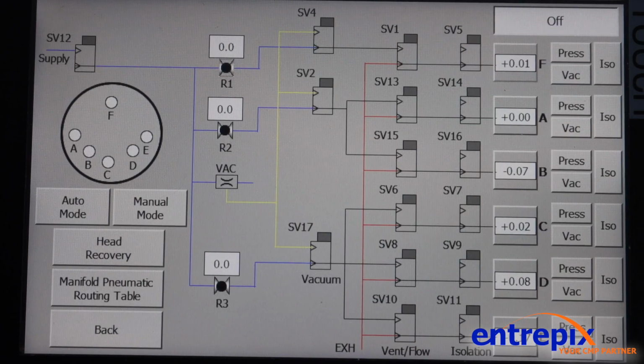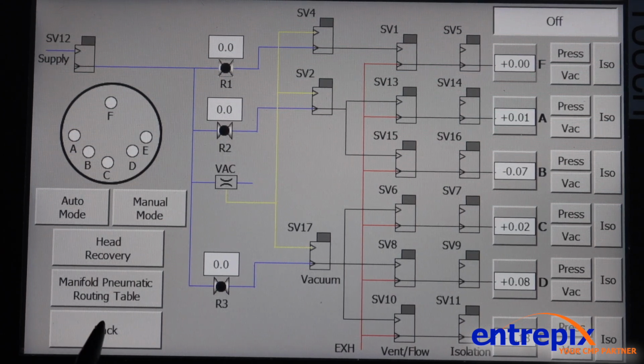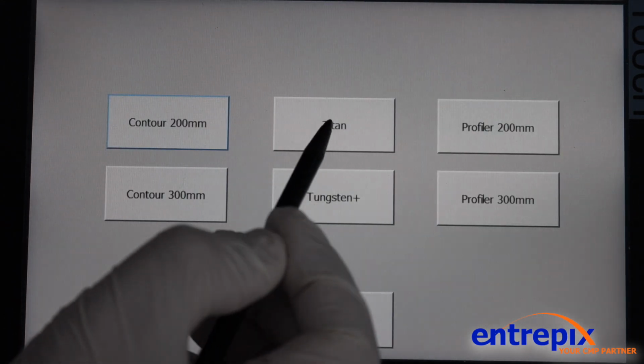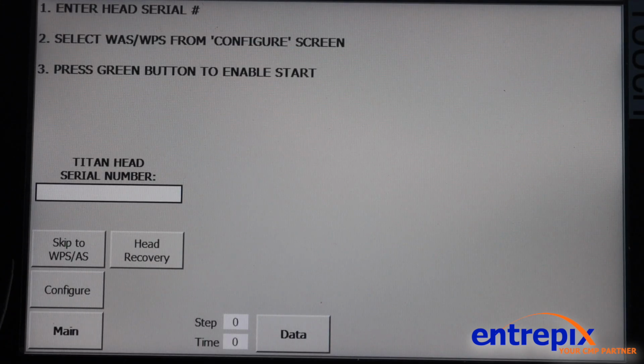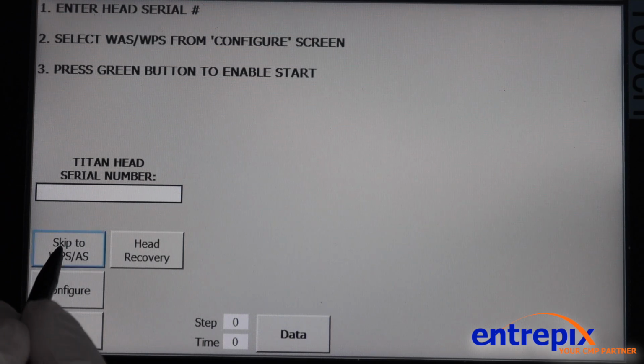Upon completion of the leak testing diagnostics, if, for example, you had failed for wafer present, wafer absent, we also have a screen that will help you diagnose that particular portion. Moving back to the main testing screen for your head, we have a button that's available for skip to wafer present, wafer absent. This would eliminate the leak testing portion of the test and move you directly to and prompt you to place a wafer onto the head for testing the wafer present, wafer absent portion.